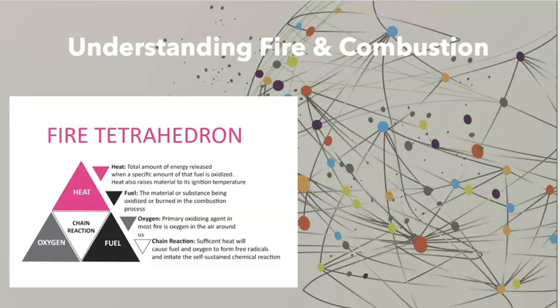A foam extinguisher creates a barrier around the combustible materials and cuts off the supply of oxygen. A water extinguisher is going to lower the temperature below the ignition point. For a flammable liquid fire, it would remove or divert the fuel. A flammable liquid fire, we would use not water but a Class K or Class B, which is going to remove or divert the fuel or cover it.